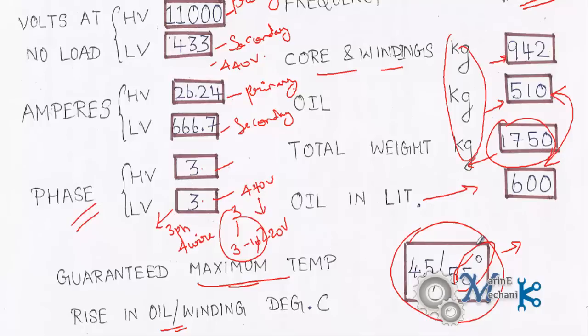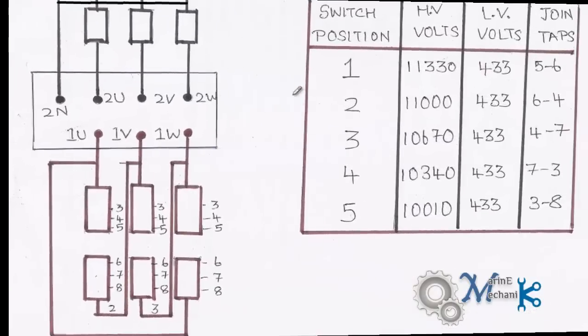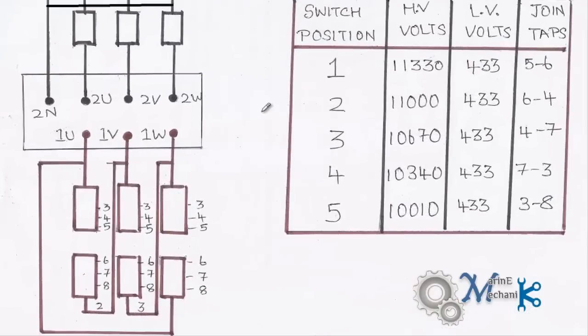Now let's see how are the taps and what are the switching tap positions. The nameplate details also have the switch tapping positions. In my previous video you have seen where the switch tapping changeover position is located. We had something like a round structure with a selector with 1, 2, 3, 4, and 5 taps or 5 positions. So these 5 positions indicate exactly this one. It's given in the nameplate detail.